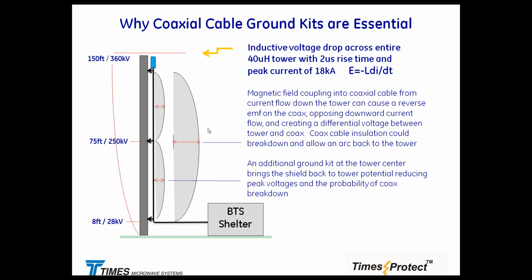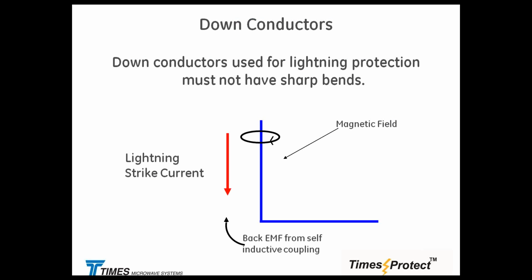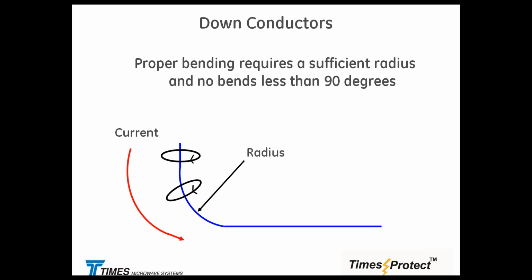The rule of thumb is to do them every 75 feet. Many people follow this format, many do not. Whatever we are doing, let's make sure we avoid a very sharp bend, because you don't want to add any more impedance or inductance into anything hanging above the ground. So always remember that a forgiving radius is the best way to go.